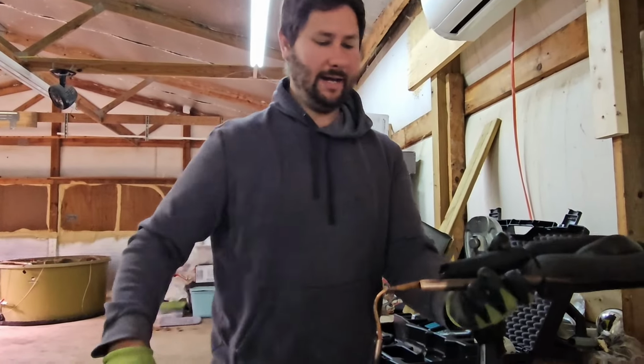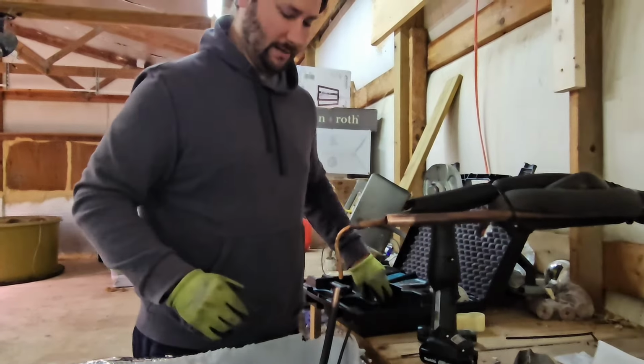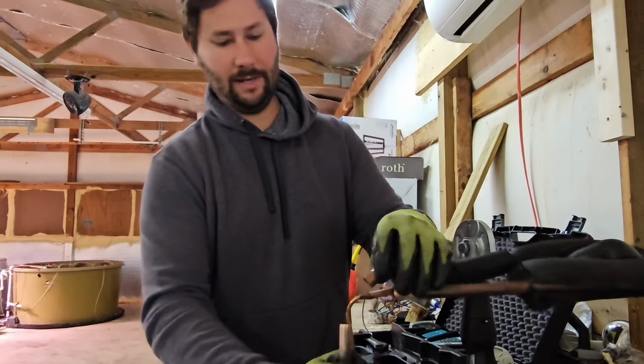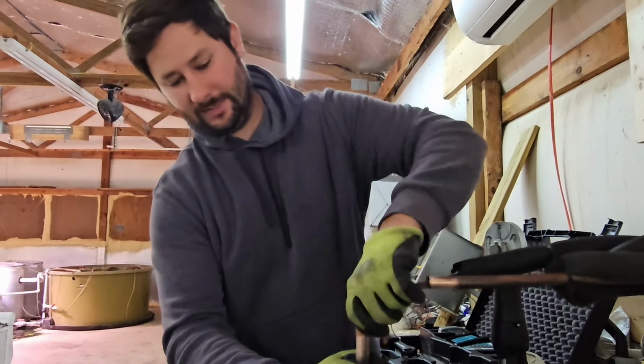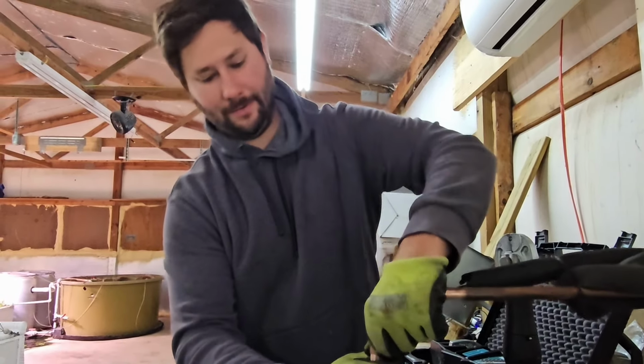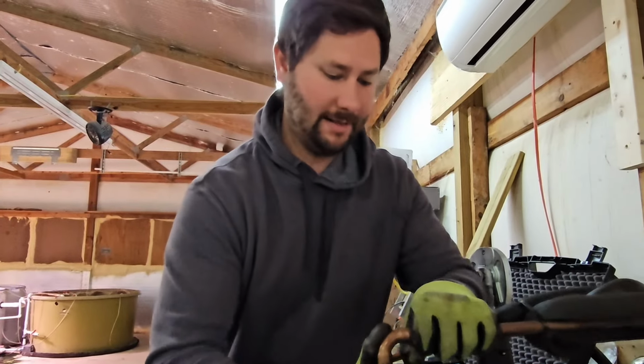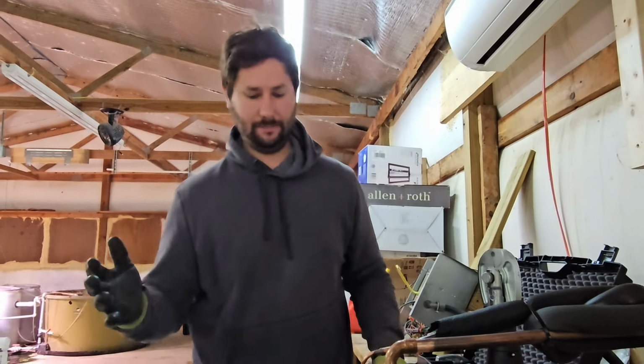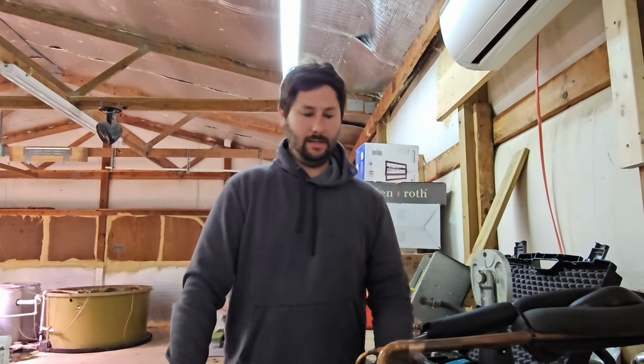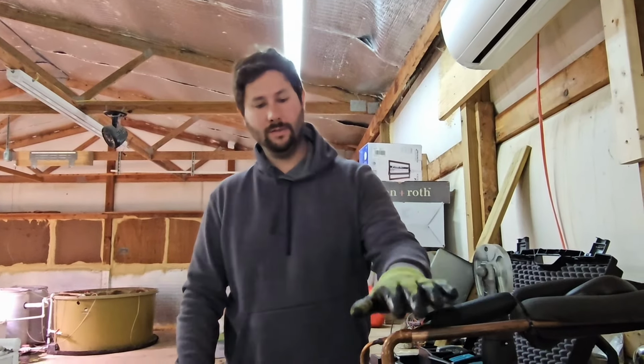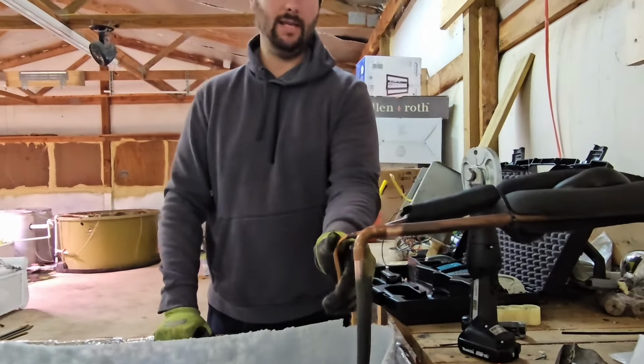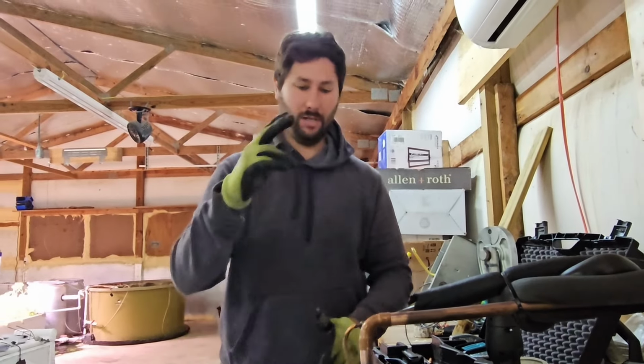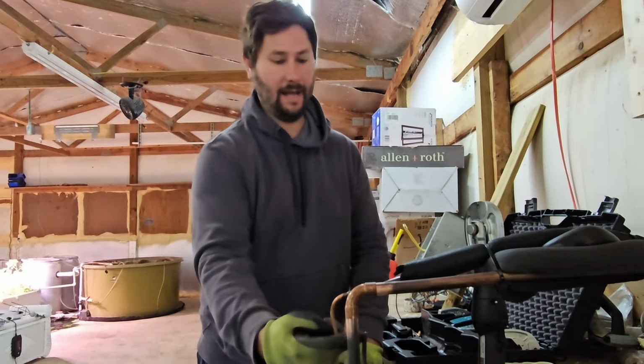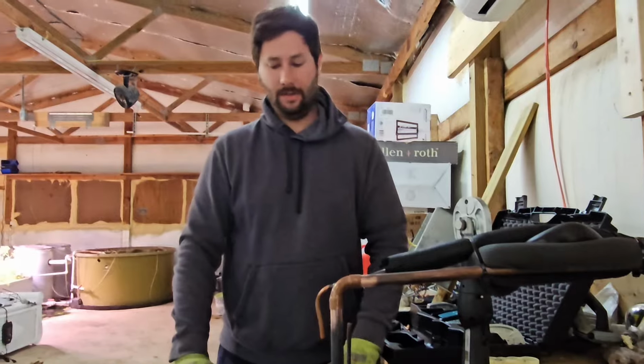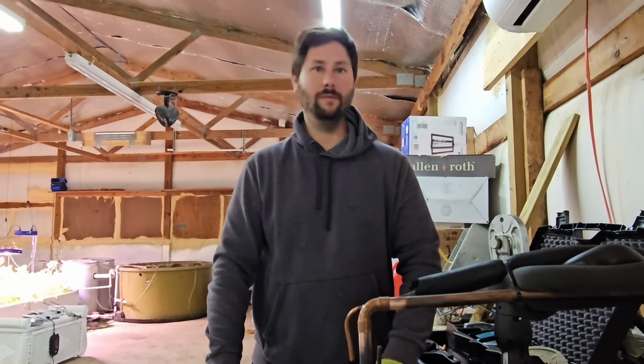We're ready to tie in the coil, so I'm sanding off those connections, and I'm going to connect this 5/8 90 from my line sets to my coil connection. I've got the heat pump outside already wired in, and I'm going to braze this connection, then leave this one and blow through the line and back out here just to clean out anything that could be harmful.